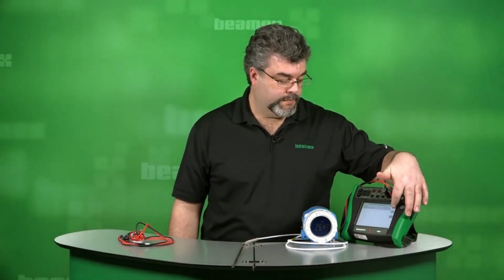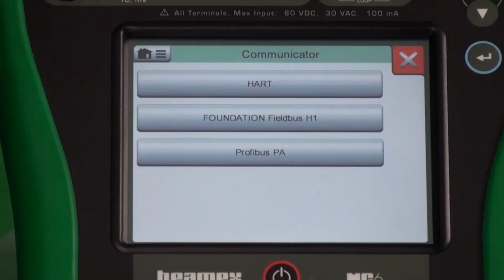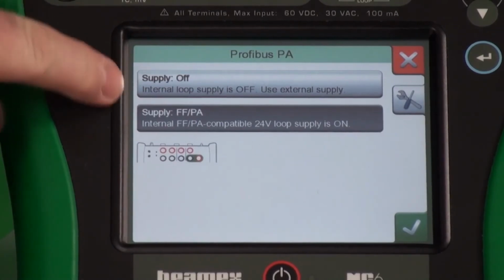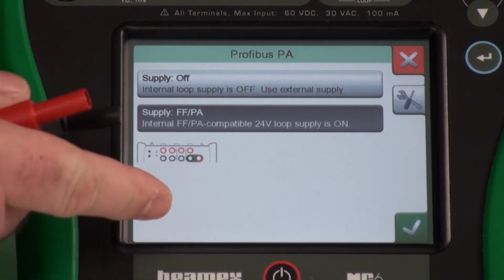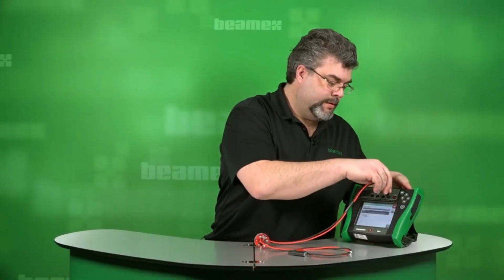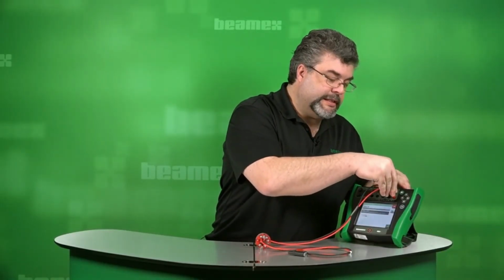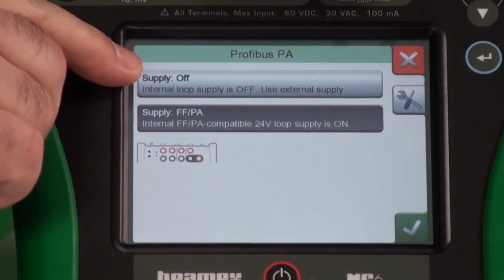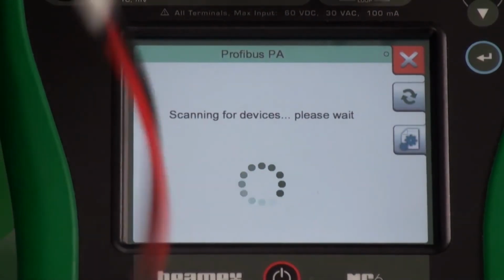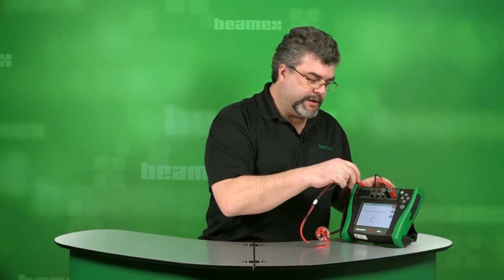As far as for our next steps, let's look at Profibus. I'm exiting out of the communicator at this point, so let me make a few more connection changes and I'll get our Profibus transmitter hooked up. Next, let's hook up Profibus. So if we don't remember where to hook up, we just follow the visual aid. If we don't need the calibrator to provide loop power, then we pick the top one, supply off, but we do want loop power. I'll just hit the check, which also includes the 50 ohm resistance. In this case, I'll go ahead and hook up the input side to our RTD.